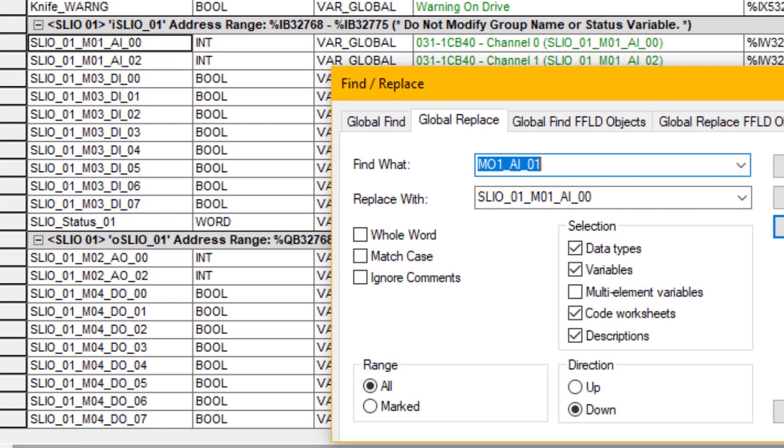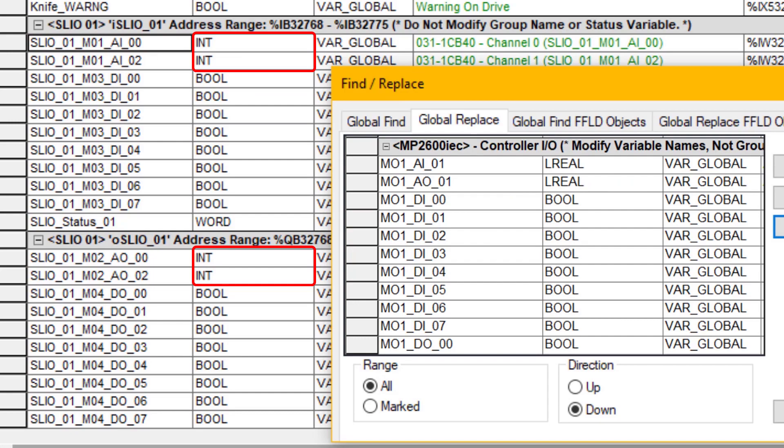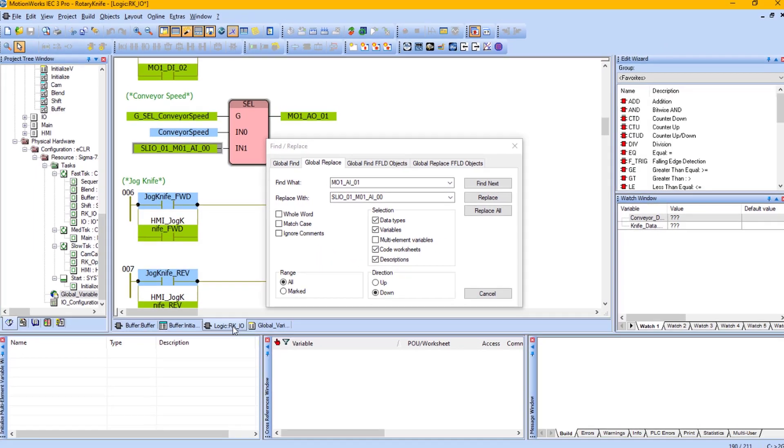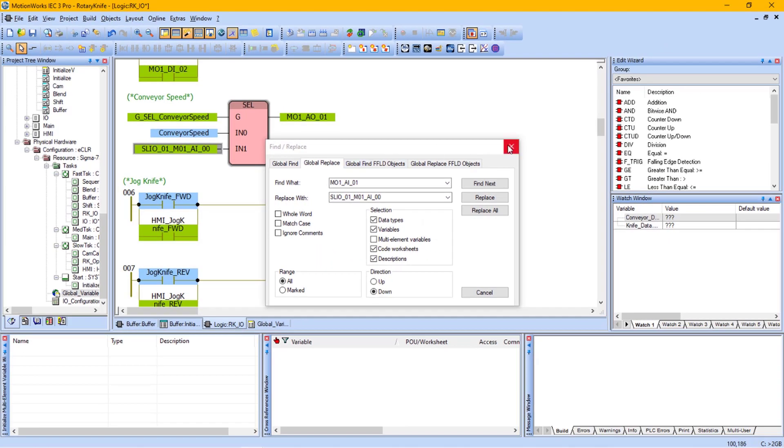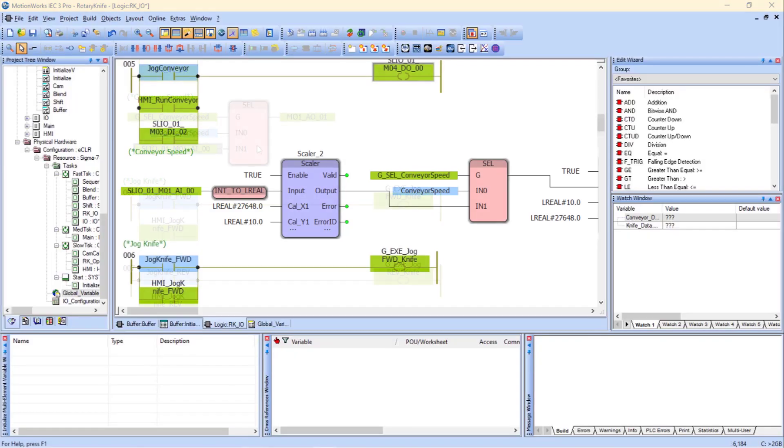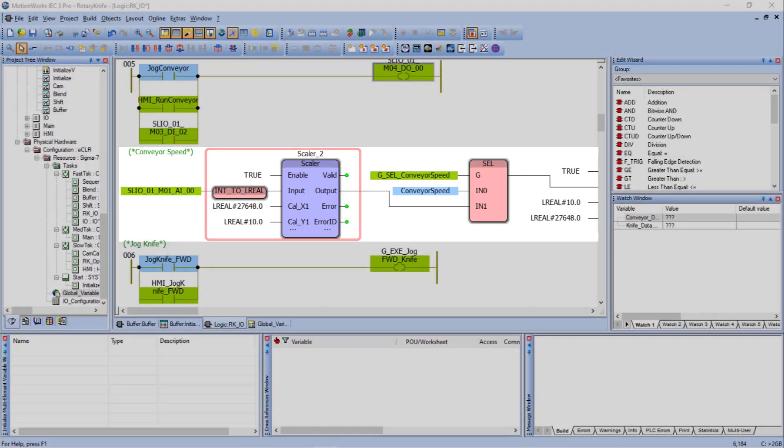One thing to be aware of is that the MP2600 IEC analog I/O is handled as an Lreal value, where the SLIO analog I/O is handled as an integer. So going back into RKIO, conversion blocks need to be added for the analog input and output signal.